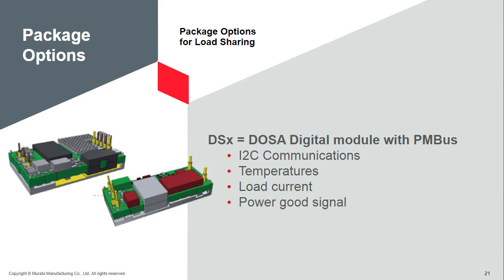So in the event that, in an isolated location, you have a power module failure, that information can be reported back to headquarters, and you can get somebody out there to fix the failed power module. But there's much more that the PM bus can do, including loop stability and many other features that you can access that are fully described in the data sheet. And again, this would be a whole other presentation to review the PM bus process.